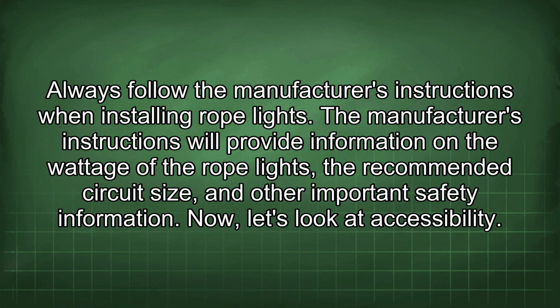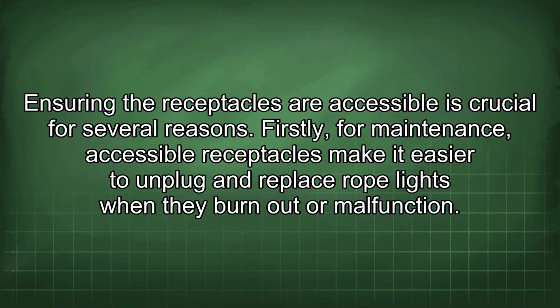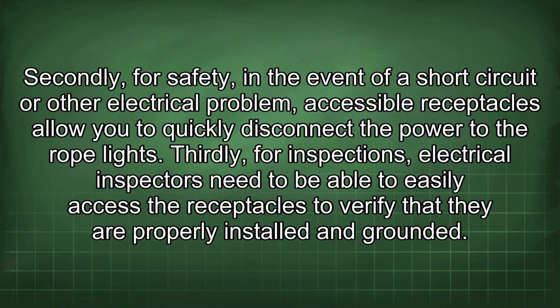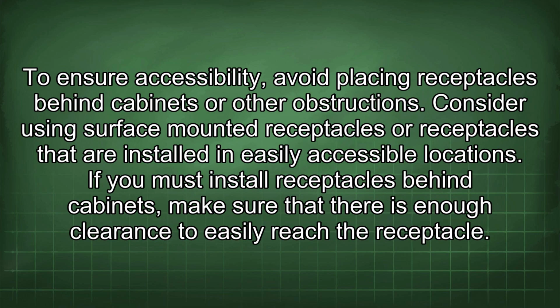Now let's look at accessibility. Ensuring the receptacles are accessible is crucial for several reasons. Firstly, for maintenance, accessible receptacles make it easier to unplug and replace rope lights when they burn out or malfunction. Secondly, for safety, in the event of a short circuit or other electrical problem, accessible receptacles allow you to quickly disconnect the power to the rope lights. Thirdly, for inspections, electrical inspectors need to be able to easily access the receptacles to verify that they are properly installed and grounded. To ensure accessibility, avoid placing receptacles behind cabinets or other obstructions.